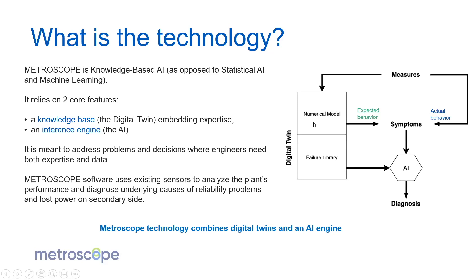For that, we not only use our digital twin to get the expected behavior of the plants, but also to get the possible states in which the plant could be because of failures. We add failures based on the expertise we have on the process, and then with this failure modeling, we try with an inference engine to match what failures could explain the symptoms we see. That is what we call diagnosis.